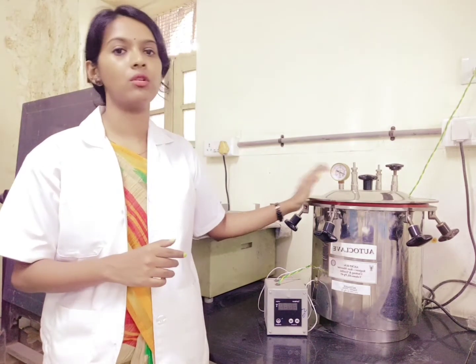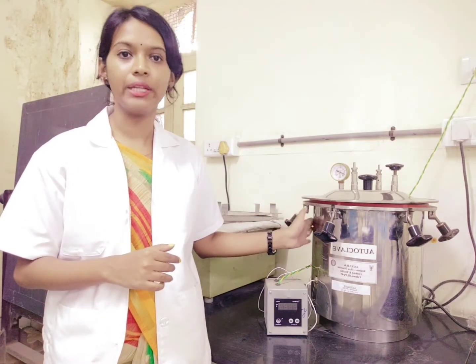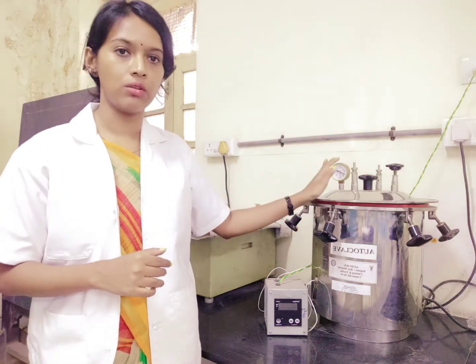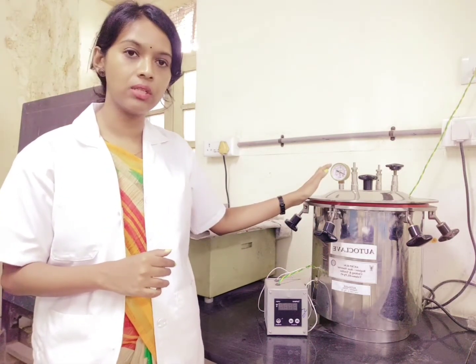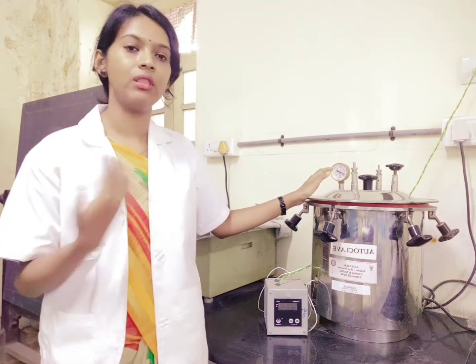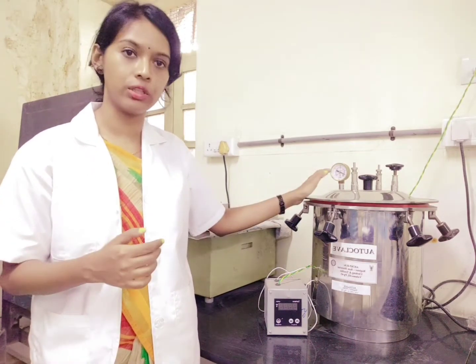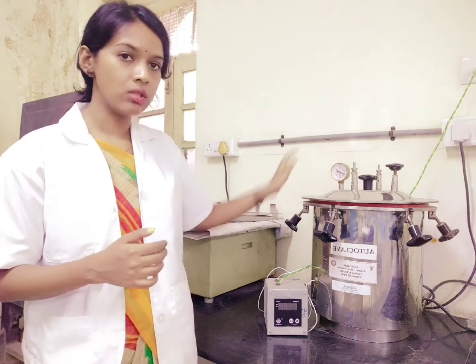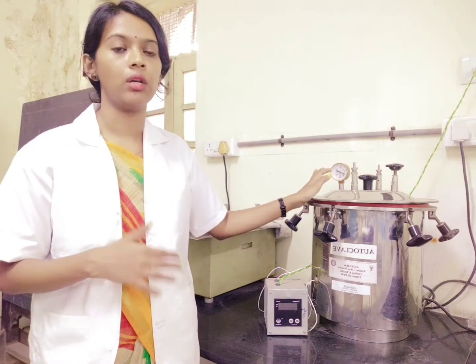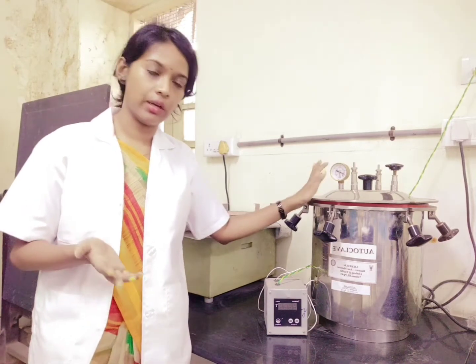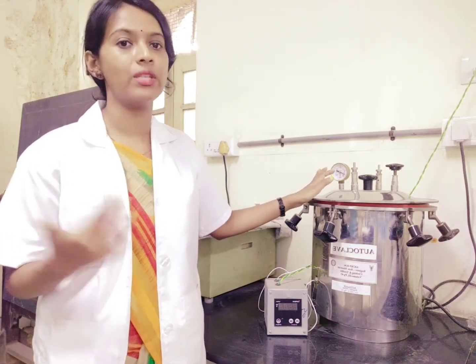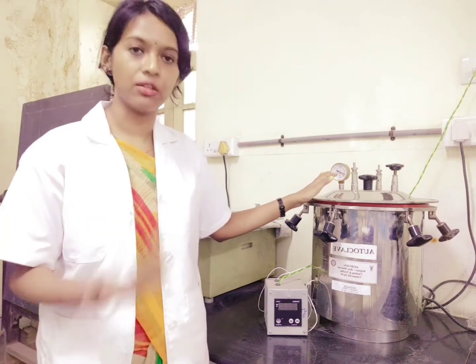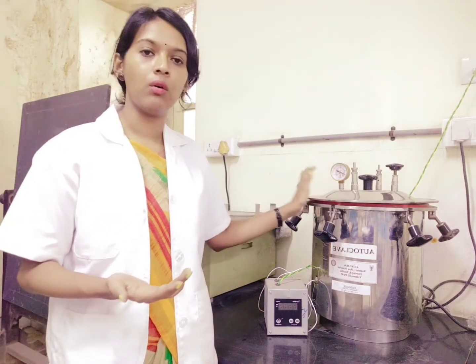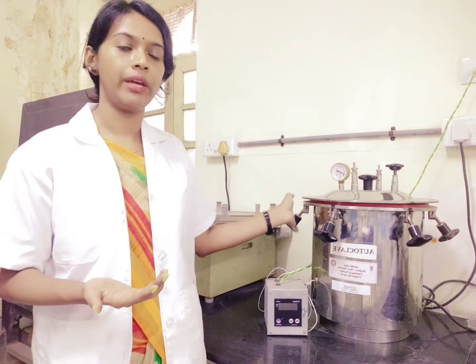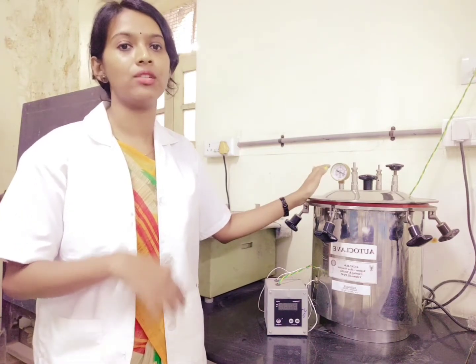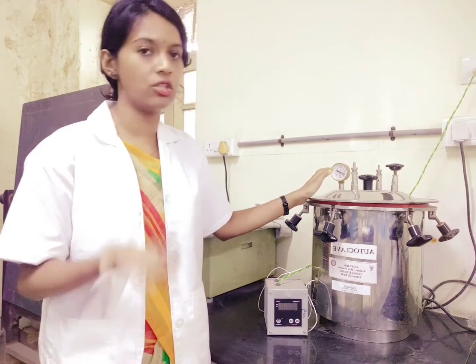That happens because of the high pressure which is generated inside the instrument. Once you turn on the instrument, the temperature will automatically increase, and as the temperature increases, the pressure also increases. So these are directly proportional to each other. Now, the sterilization process in the autoclave takes place in three phases. First is the purging phase, where the cool air present inside the autoclave is removed.